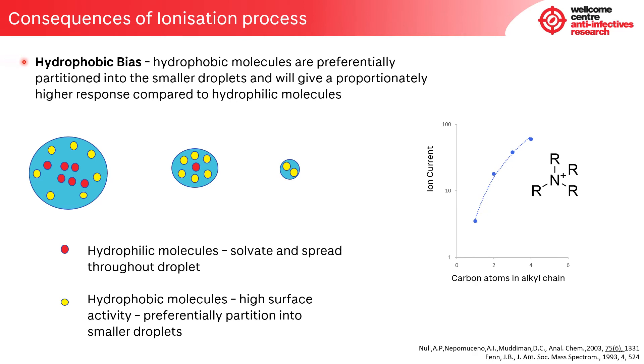There are a number of consequences of the ionization process, and the first we look at is that of hydrophobic bias. It's been shown that hydrophobic molecules are preferentially partitioned into the smaller droplets and therefore give a proportionally higher response compared to hydrophilic molecules. The hydrophilic species tend to be solvated and spread throughout the droplet, whereas the hydrophobic molecules are surface active and tend to be distributed at the surface. As the droplet splits into smaller droplets, those species at the surface are proportionally taken up to a higher degree, resulting in a higher proportion of hydrophobic molecules in the smaller droplets, and this is repeated as the droplet decreases in size.